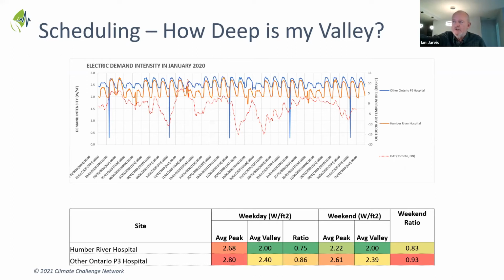What's important about this interval meter chart? This is 24-hour monitoring of the electric meter on the hospital. We've compared it with the blue line, another P3 Ontario hospital of about the same vintage and system configuration that doesn't have anything like that degree of scheduling. You can see the peak demand difference between the blue and the orange, and this is day after day, week after week.